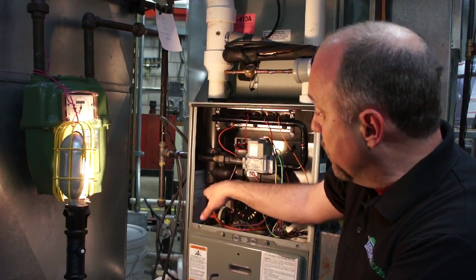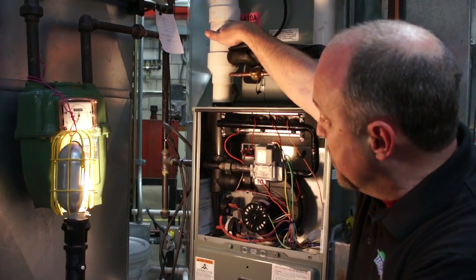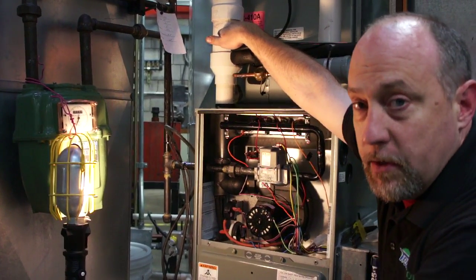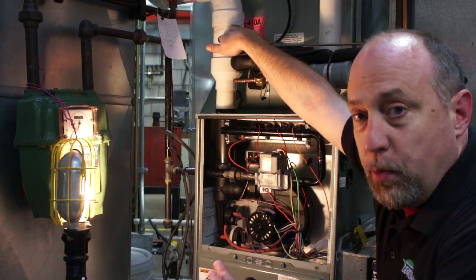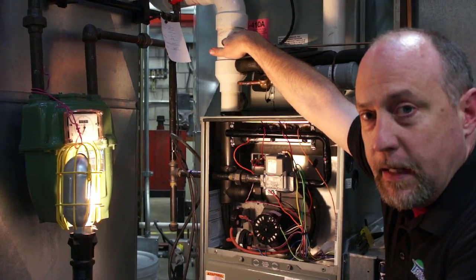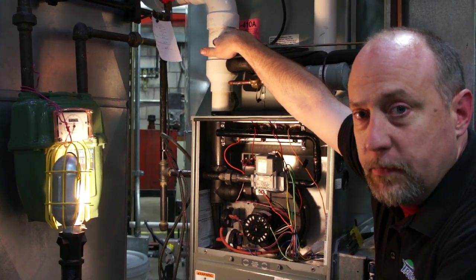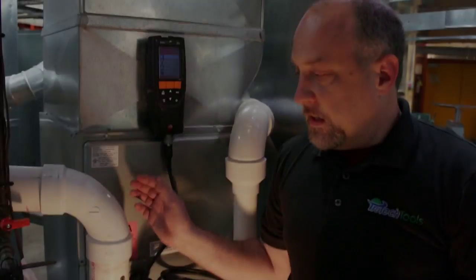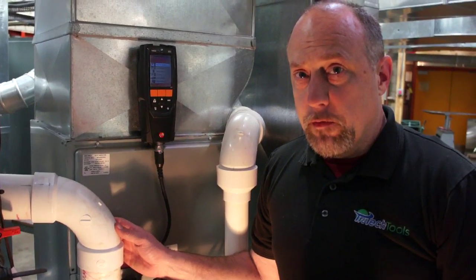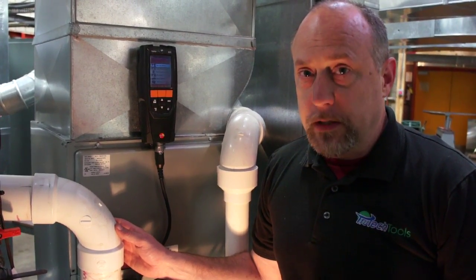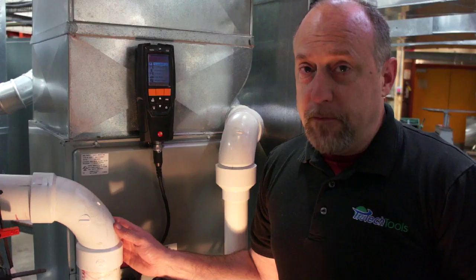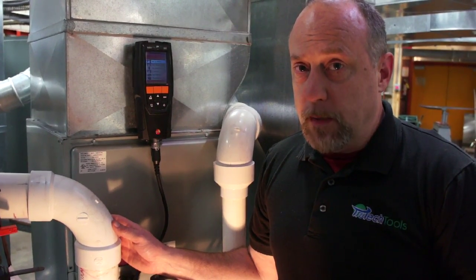So ideally here we want to have about 18 inches of space to give that air time to slow down, so that we read pressure and we're not influenced by the velocity of the gas in the flue pipe itself. This is a 90 plus with a category 4 vent system, which means it's under positive pressure, which means that we have to make sure that flue pipe is sealed after we do our combustion test.